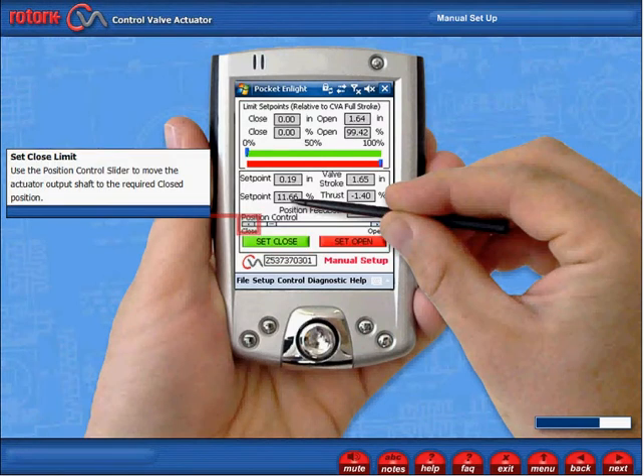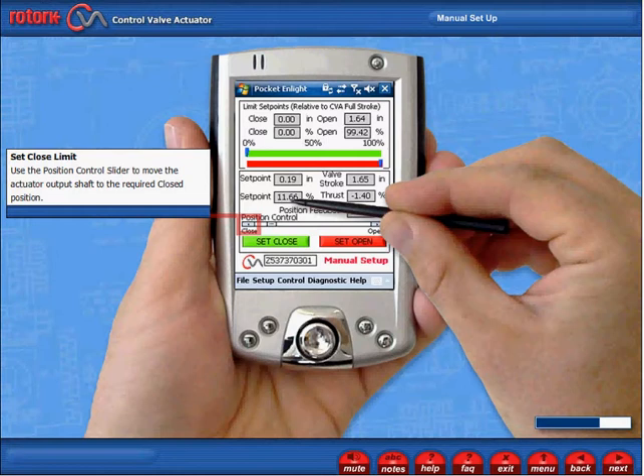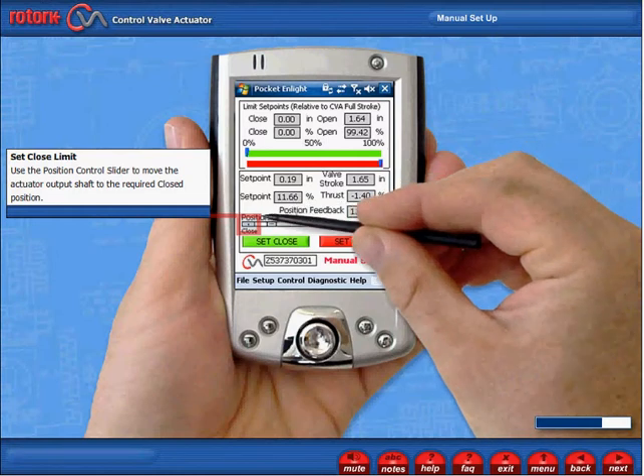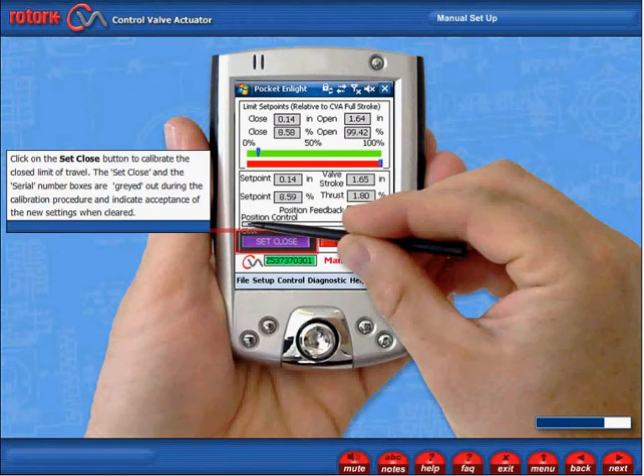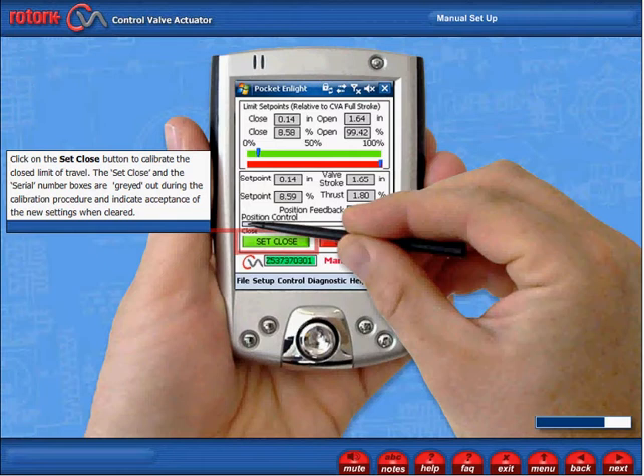Set Close Limit. Use the position control slider to move the actuator output shaft to the required closed position. Click on the Set Close button to calibrate the close limit of travel.